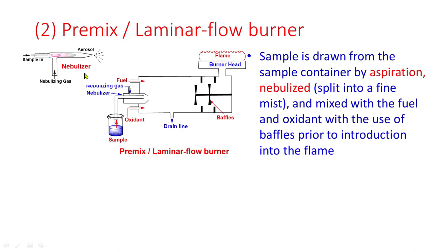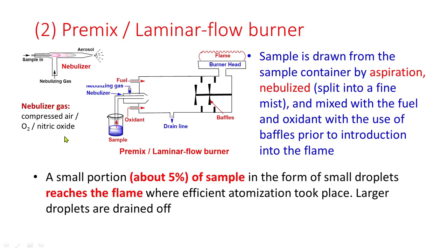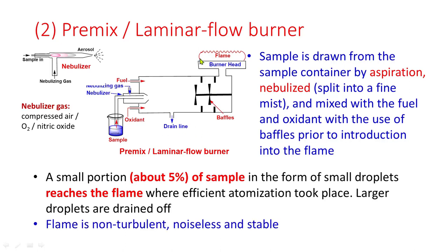This is the nebulizer. The sample enters from one side and nebulizing gas is forced through so that the sample is converted into an aerosol. The nebulizing gas can be compressed air, oxygen, or nitrous oxide. Only about 5% of the sample in the form of very small droplets reaches the flame, where efficient atomization takes place. Larger droplets are drained out. The resulting flame is non-turbulent, noiseless, and stable.